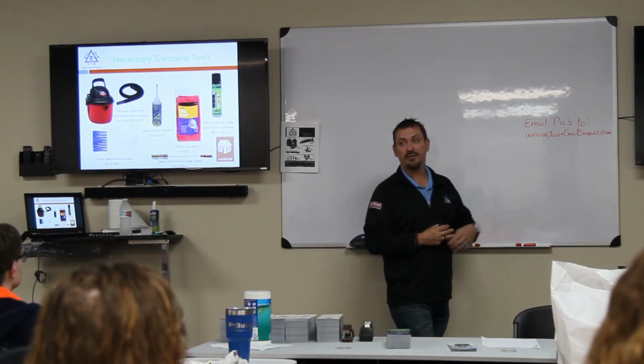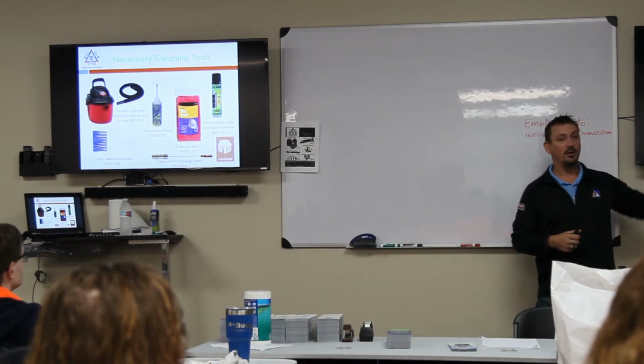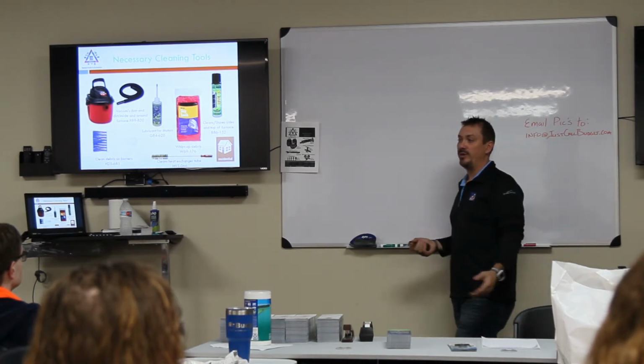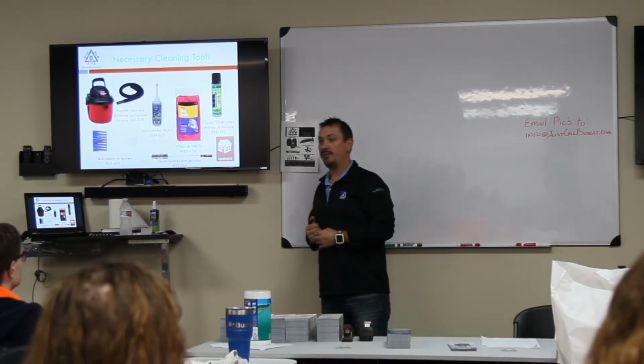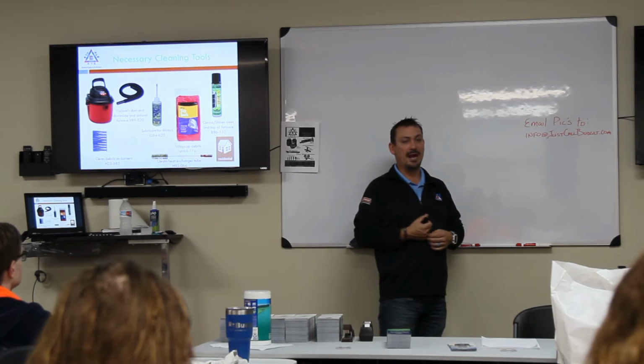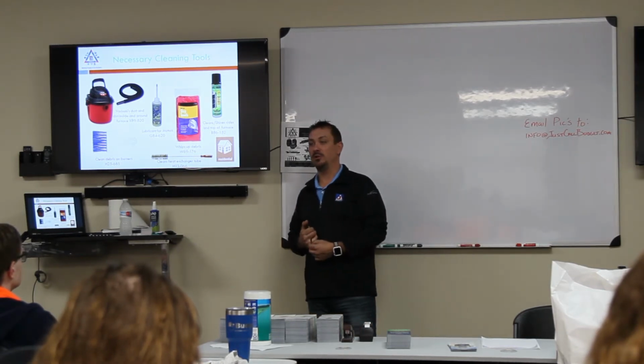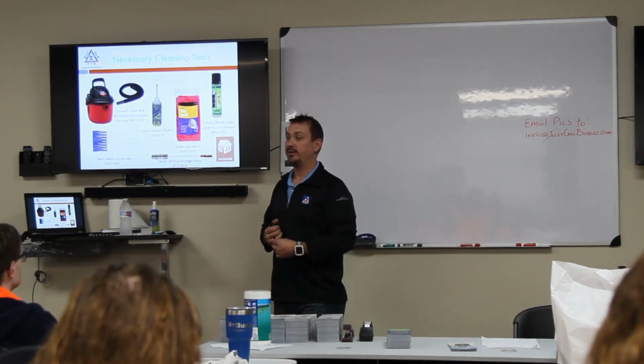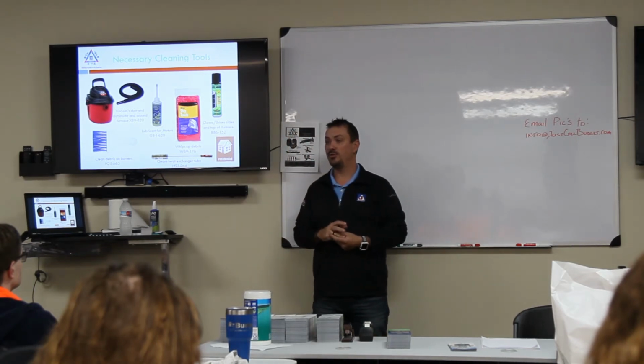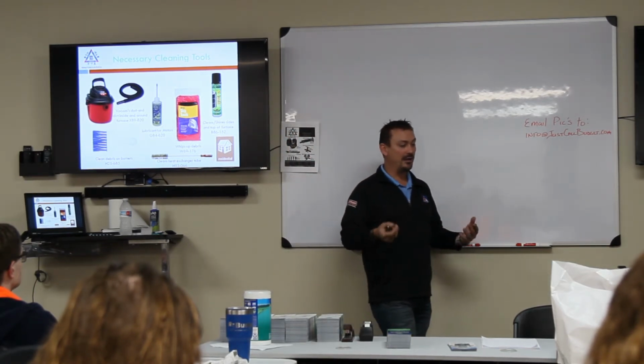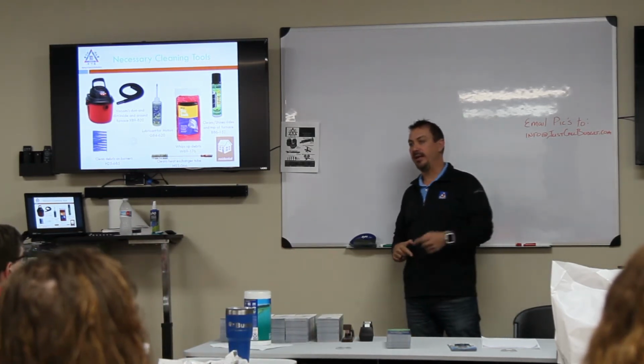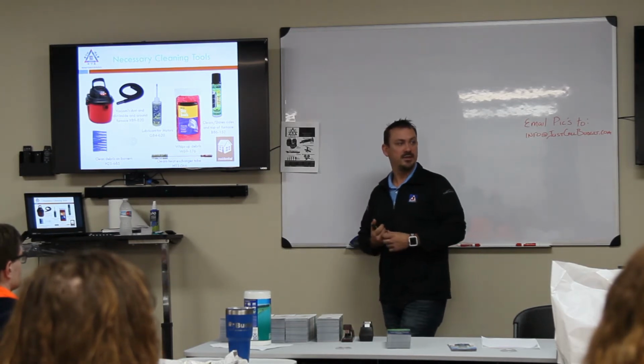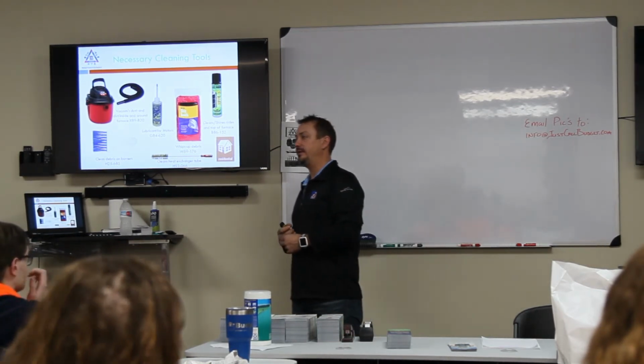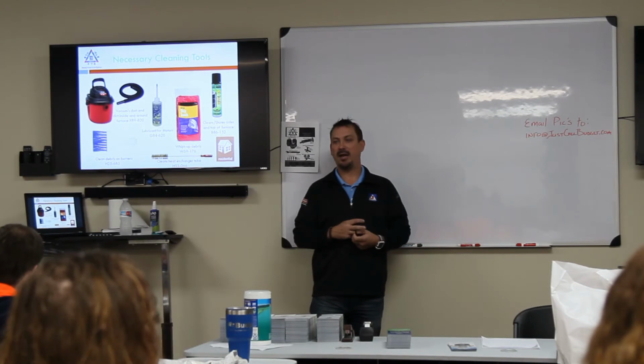Let's face it, most everything up here, except for maybe the oil, doesn't really affect the performance of that equipment. Everything that's up here is really for eye candy for that customer. It's making that unit look nice and shiny, because for all intents and purposes, when you go over there for a clean and check, they're not looking inside that equipment to see if you adjusted the gas pressure. They're not looking to see if the flame sensor is now nice and clean and going to be operating and not fail.